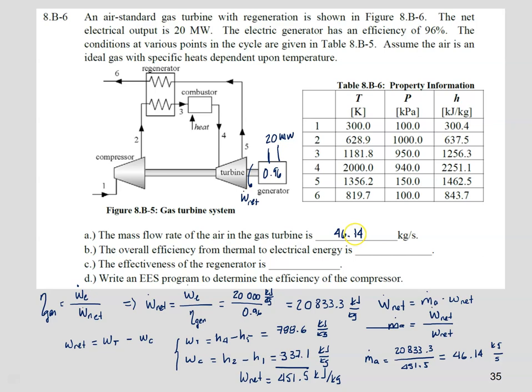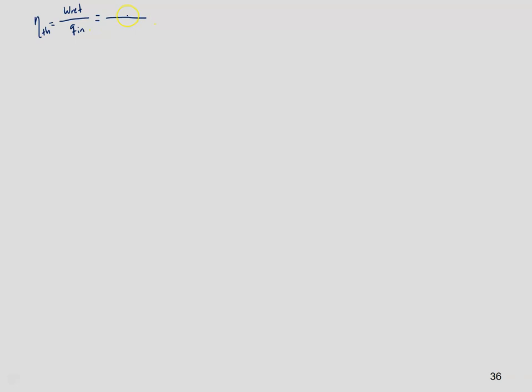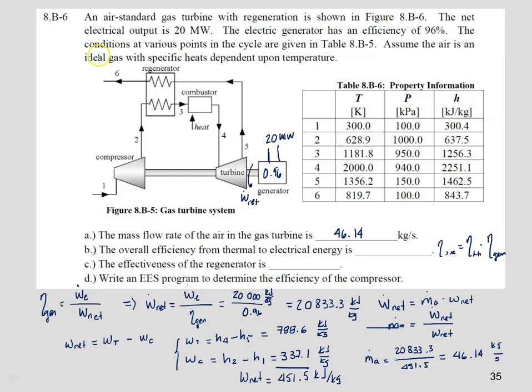Now we need to find the overall efficiency. To find it, we need to multiply all the efficiencies involved, including the thermal efficiency. The thermal efficiency is defined as the net work divided by q_in — it doesn't matter whether we use power or specific quantities because the mass flow rate cancels. We already know the net work is 451.5 kilojoules per kilogram, but we need to find q_in.